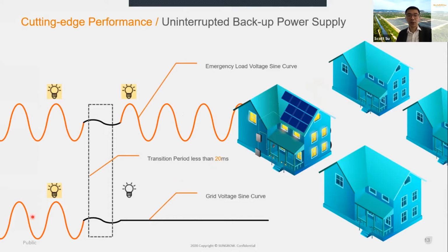So here is the grid voltage sine curve, and from here the grid has a power outage, and the grid voltage cannot continually supply the house loads. But here are Sungrow hybrid inverters. We can still generate this sine voltage curve to supply the house loads, emergency loads. And from here to here is the transition period, and we can do it in less than 20 milliseconds. Here, I have a short video to show you this seamless transfer capability.